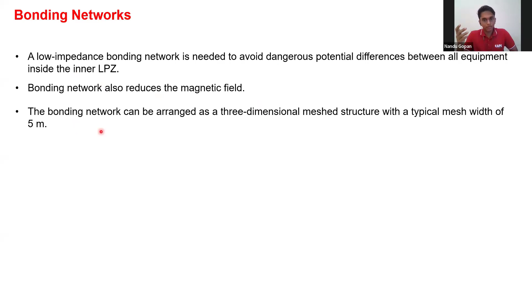So why do we need bonding networks? A bonding network creates a low impedance bonding network to avoid dangerous potential difference between all equipment inside the inner LPZ. A bonding network also reduces the magnetic field. The bonding network can be arranged in a three-dimensional meshed structure with a typical mesh width of 5 meters.